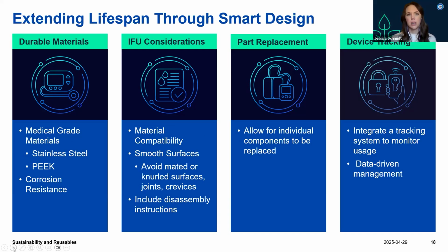So the first would be durable materials. So using high quality medical grade materials can greatly improve durability. Materials such as stainless steel, titanium, or PEEK have a high resistance to external factors such as corrosion and chemical resistance, which is critical in environments that involve repeated sterilization cycles. Next, we have IFU considerations. So it's important to ensure compatibility between your materials and the reprocessing methods. Designing devices with reprocessing in mind can help alleviate potential issues down the road. Complex features like knurled surfaces, mated edges, or crevices can all pose challenges when it comes to reprocessing. And just as important is also to include clear disassembly instructions. This can make reprocessing and servicing easier and more effective.